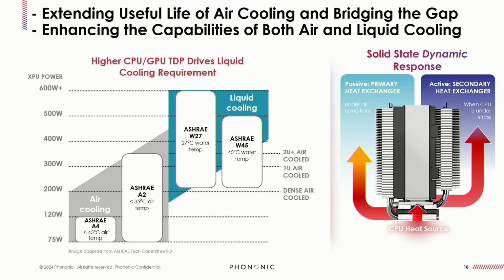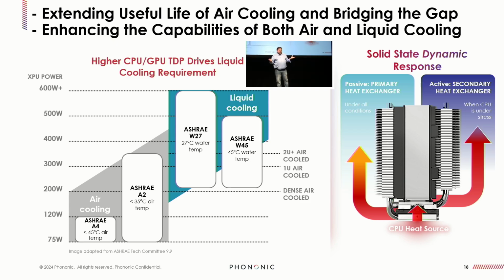But remember this from before. Air cooling, water cooling, very clear limits. This is from an ASHRAE committee report that says we're sort of limited to around 400 watts with air cooling. That's true if you have a purely passive application.